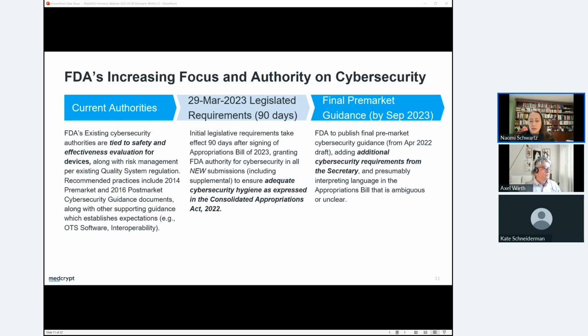Under FDA's current existing authorities, it's tied to the quality system reg and those concepts of safety and effectiveness. You're really focused on responding to the recommended practices in the 2014 pre-market and the 2016 post-market guidance documents, but you're not necessarily going to see FDA ask for all of the documentation. There are additional guidance documents like the off-the-shelf software guidance and the interoperability guidance that also apply. I would expect in the future, as the pre-market cybersecurity guidance gets finalized, that you will start to see revisions on the others as well. Those documents have been the direction finding for manufacturers, but for certain devices moving forward, those are requirements, not recommendations anymore.